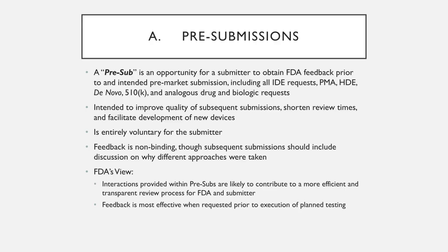Now, the pre-sub, which I often hear being synonymous with the Q-sub process, so much that Q-sub and pre-sub are sometimes even used interchangeably, stands for pre-submission, and is the main pathway for a medical device company to get feedback prior to any intended submission for any of those pathways that might require an IDE. So including the premarket approval, 510(k), the humanitarian device exemption, and the de novo pathway, and also applicable to their analogous drug and biological requests.